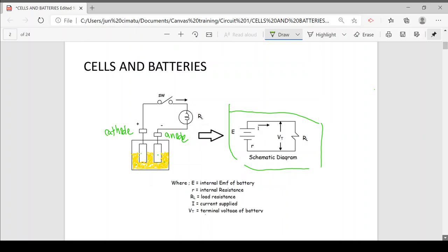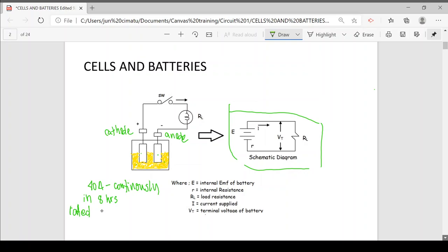For example, if we have a battery that can discharge at 40 amperes for 8 hours, then the battery is rated as 40 times 8, or 320 ampere-hours. That is how we rate a battery.